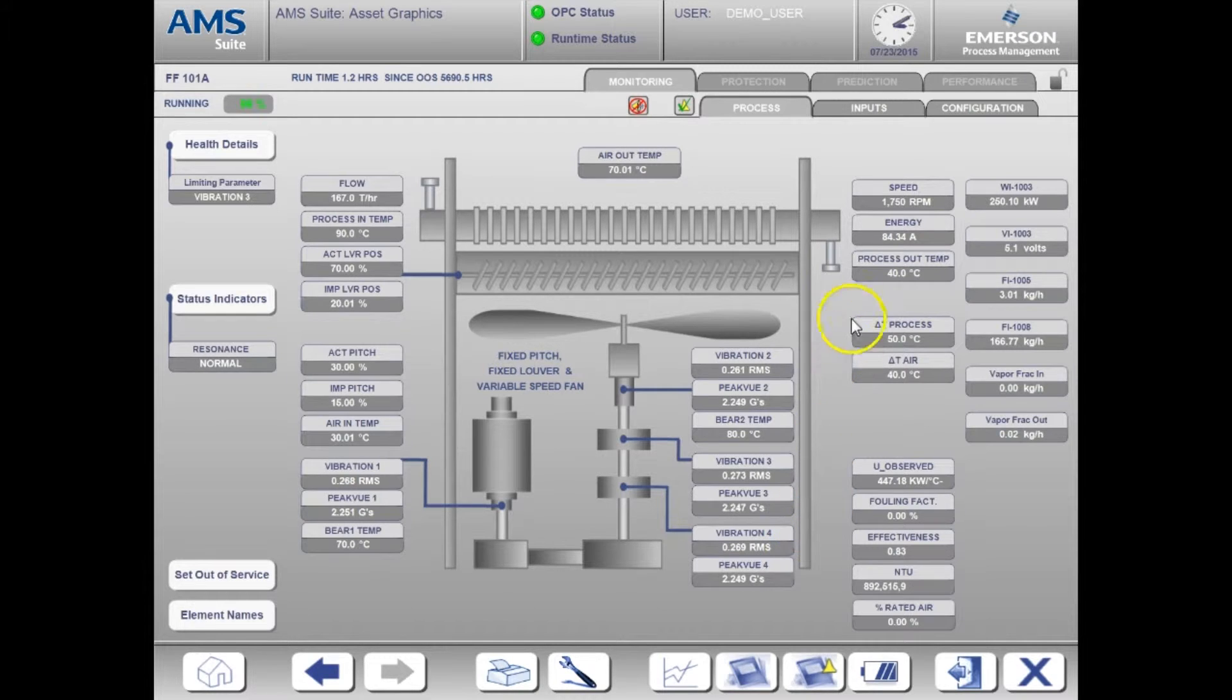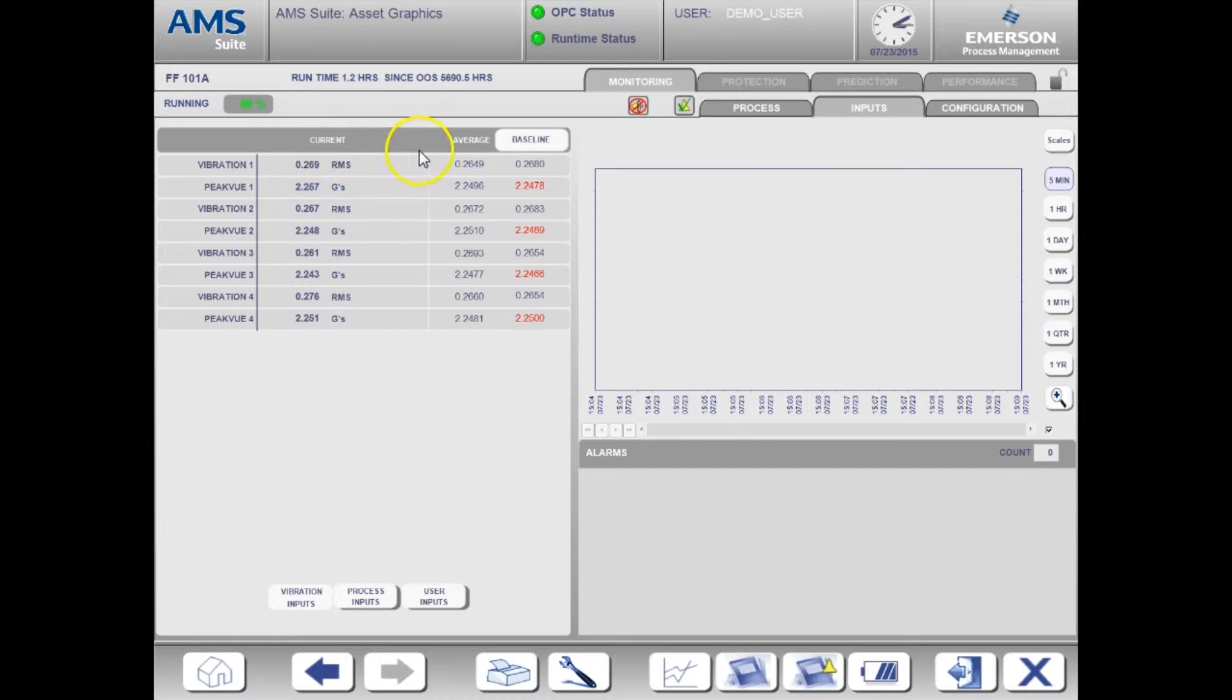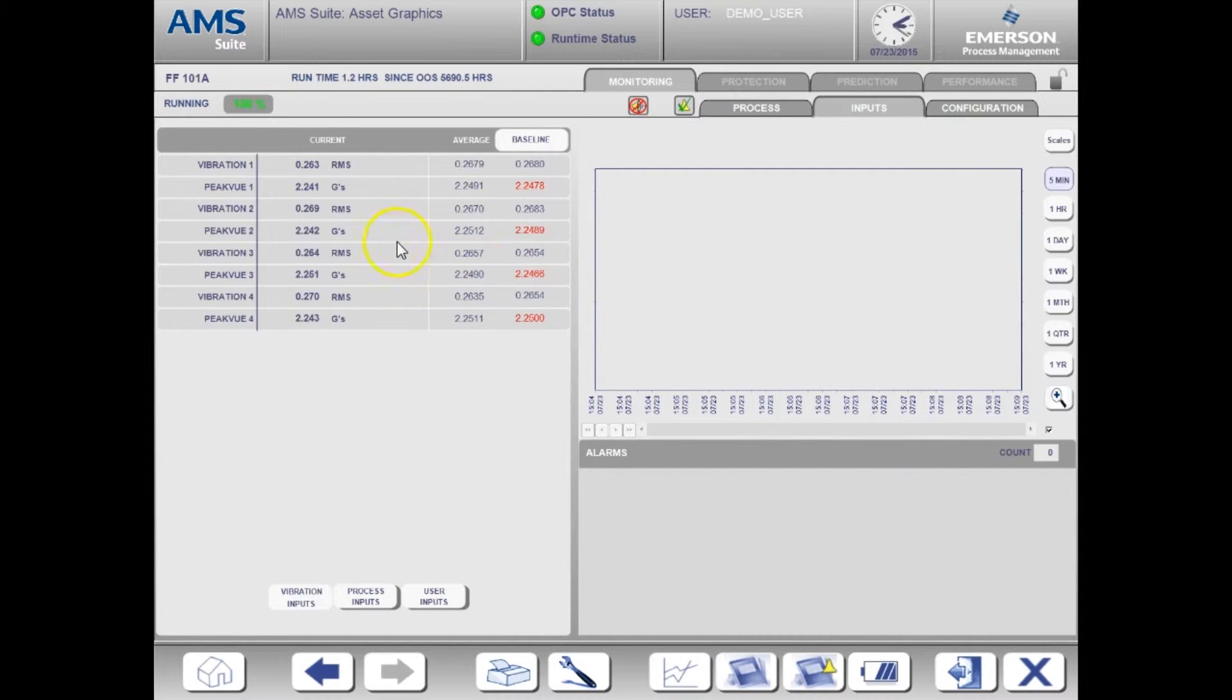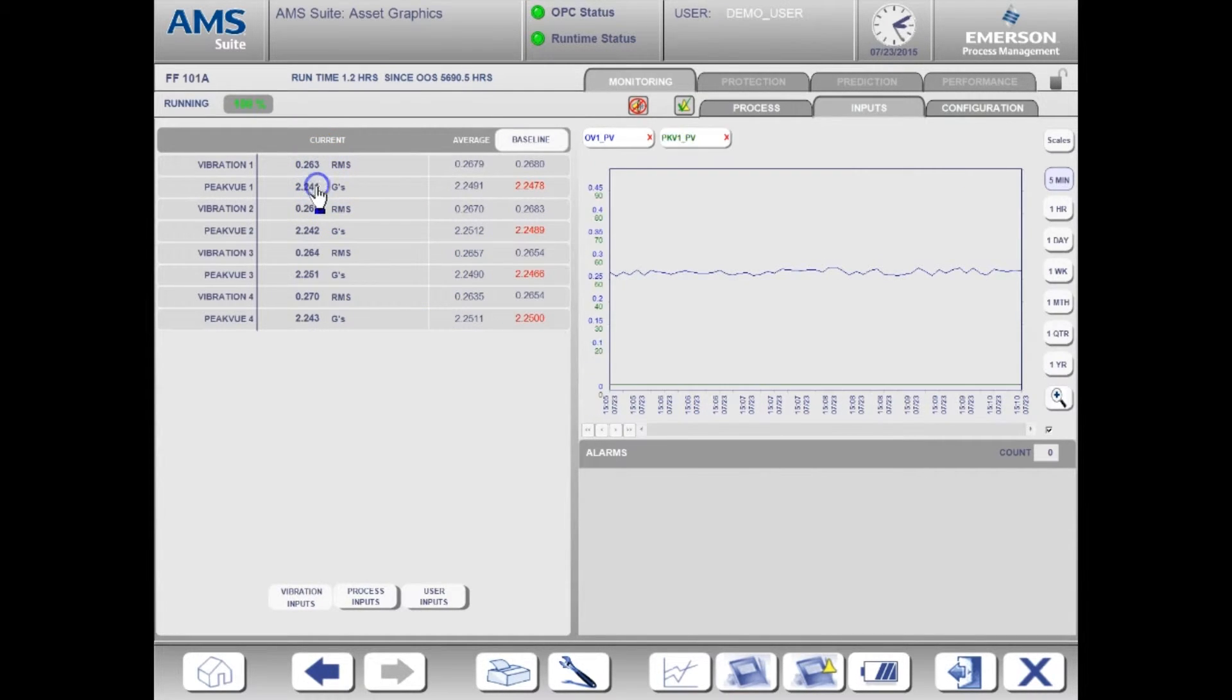Let's now go over to the inputs tab. On the inputs page you can see the current value, the average, and the baseline value for each input. There's also a trend window available here. I'm going to add the overall and PeakVue vibration values to the trend. To do that, simply click on the value for each input you would like to trend.